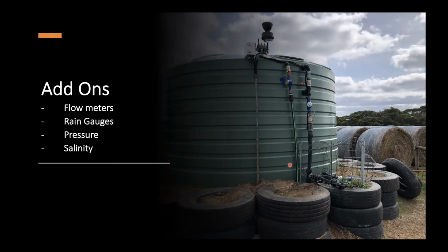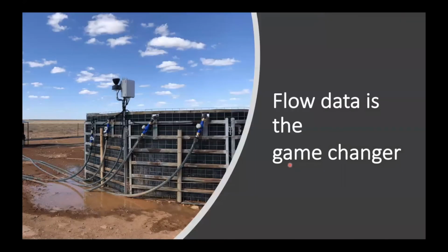Generally speaking, I think that tank level sensors by themselves are great for satellite tanks, but realistically on your main header tank is really where you want to be having a system with flow meters. For me, flow data is the absolute game changer, and I go back to it every day of the week. I think it's the best system. So in this scenario, we'll measure the flow coming into the tank, which allows you to monitor the health of your bore or solar pump. We'll report each morning the maximum flow rate. So that should be pretty consistent over time. With solar pumps, there's no point reporting minimum because they'll be zero overnight. And then we have a flow meter on the outlet, which allows us to get some leak detection.